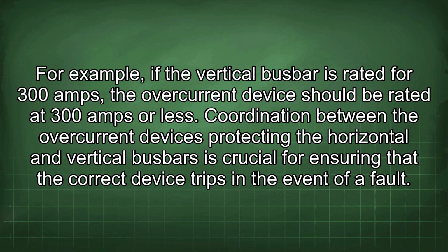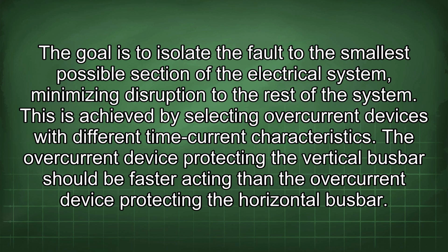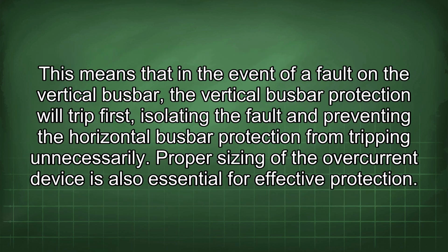Coordination between the overcurrent devices protecting the horizontal and vertical busbars is crucial for ensuring that the correct device trips in the event of a fault. The goal is to isolate the fault to the smallest possible section of the electrical system, minimizing disruption to the rest of the system. This is achieved by selecting overcurrent devices with different time current characteristics. The overcurrent device protecting the vertical busbar should be faster acting than the overcurrent device protecting the horizontal busbar. This means that in the event of a fault on the vertical busbar, its protection will trip first, isolating the fault and preventing the horizontal busbar protection from tripping unnecessarily.